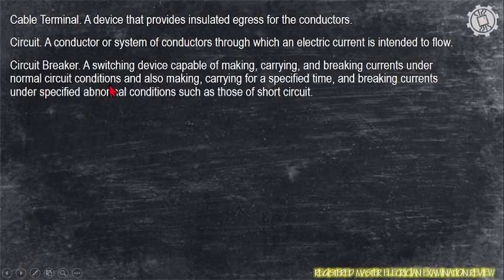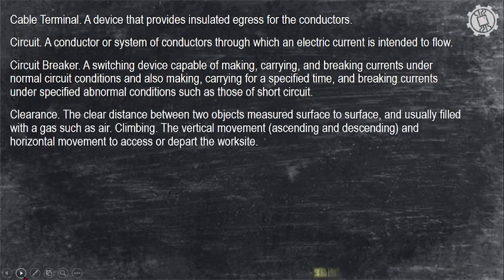Circuit breaker, a switching device capable of making, carrying, and breaking currents under normal circuit conditions, and also making, carrying for a specified time, and breaking currents under specified abnormal conditions such as those of short circuit. The circuit breaker will trip during a short circuit. It can also be turned off under normal conditions, and it could also be turned on, no, under normal conditions. So, magtitrip lang siya in abnormal conditions, especially pag meron tayong short circuit.